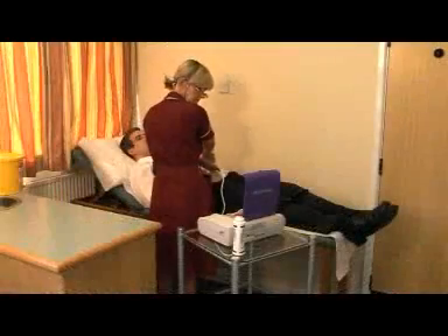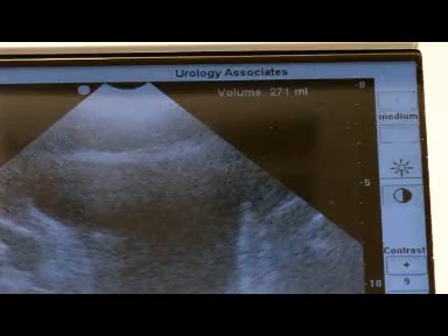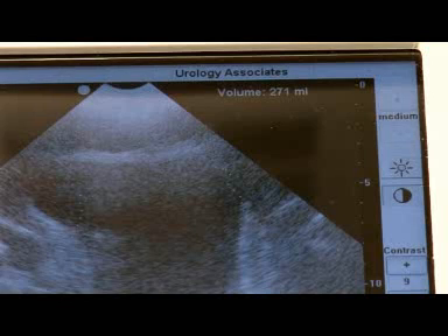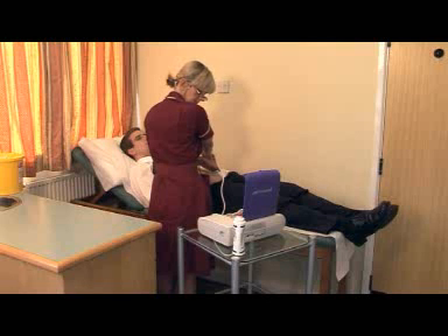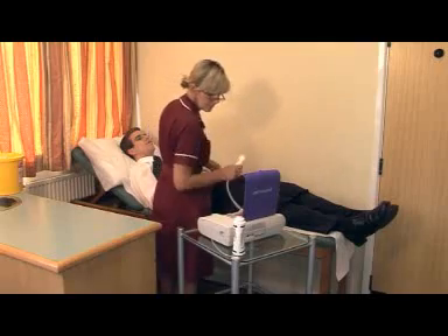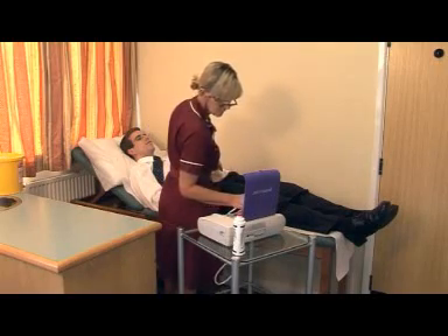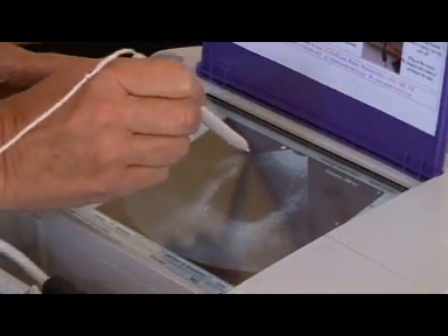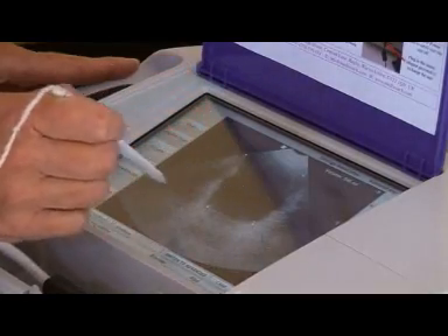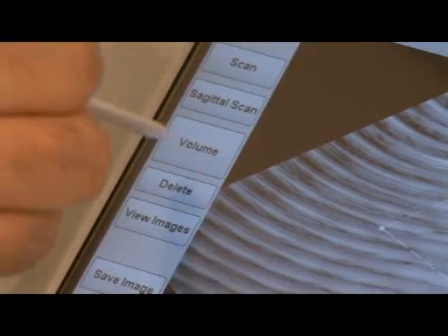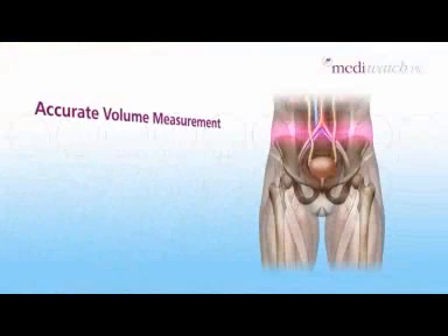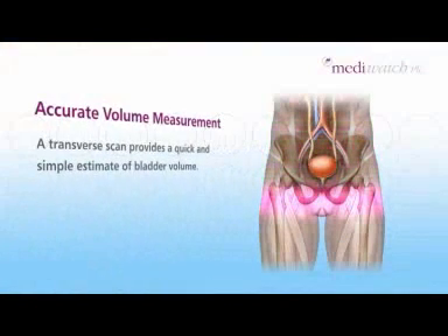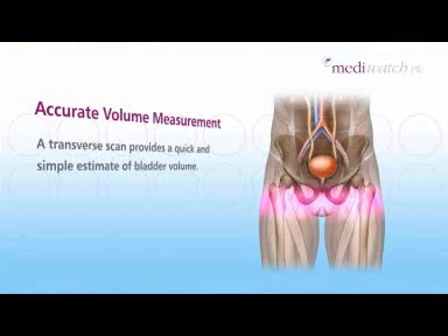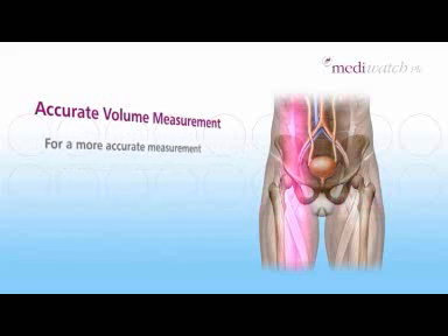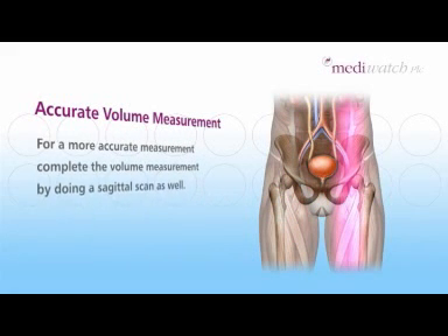If for some reason you suspect that a better picture could be found, then repeat the transverse scan until you're happy. If you feel that the automatic calculation could be improved, then touch the screen to mark 2 or more points on the bladder edge and press volume to recalculate it. A transverse scan provides a quick and simple estimate of bladder volume. For a more accurate measurement, complete the volume measurement by doing a sagittal scan as well.